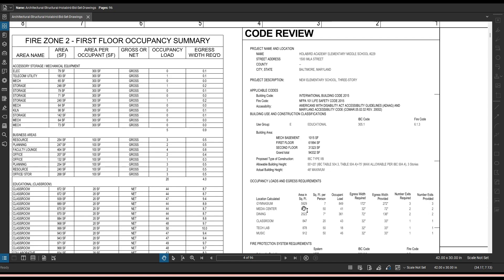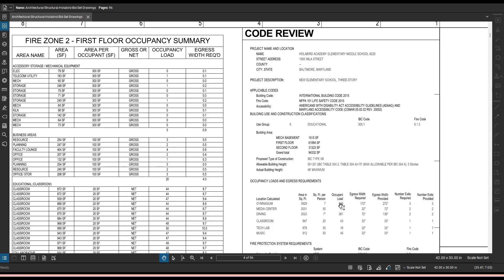Let's take the gym for instance. This lists out the size of the gym and now you have a square foot per person. So that means that if the gym was loaded to the complete max, each person should have seven square feet around them. So that's the occupancy load there in a space of 5,929. The occupancy load for people is 847 people.